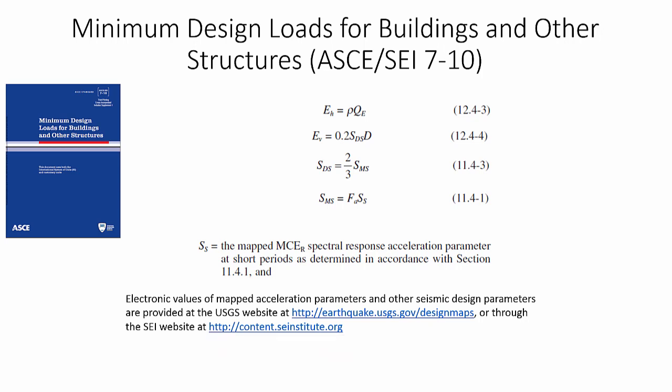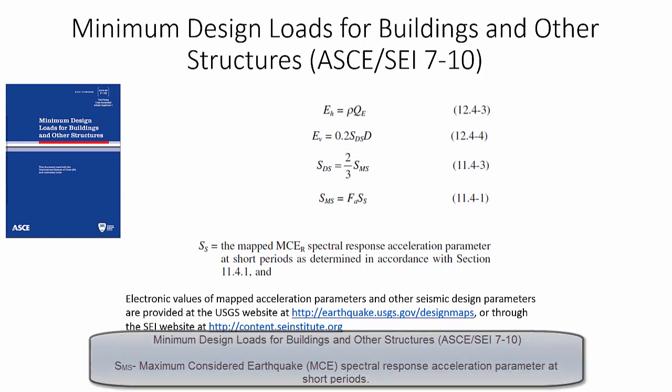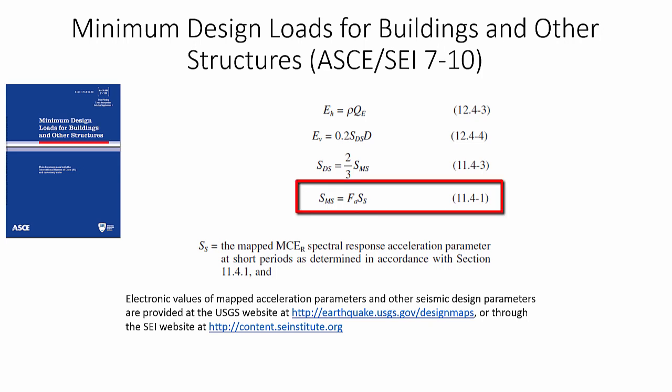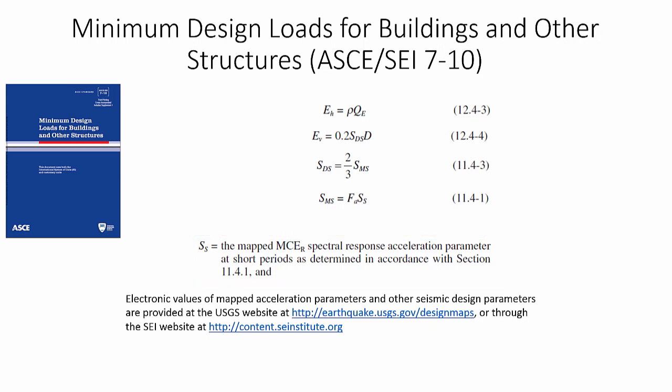The design spectral response acceleration parameter at short periods SDS is obtained by an equation where SMS is the maximum considered earthquake spectral response acceleration parameter for short periods. SMS is defined by the equation in ASCE 7 where FA is the site coefficient factor and SS is the maximum considered earthquake spectral response acceleration parameter determined from figures in the ASCE 7 standard. Note that electronic values of map acceleration parameters and other seismic design values are also available at the USGS website referenced in the ASCE 7 standard.